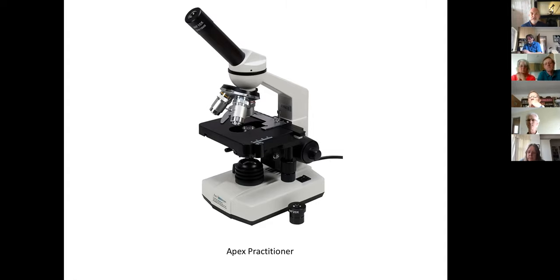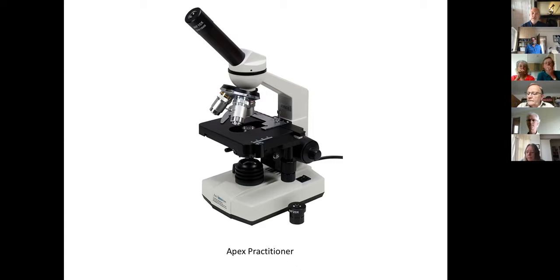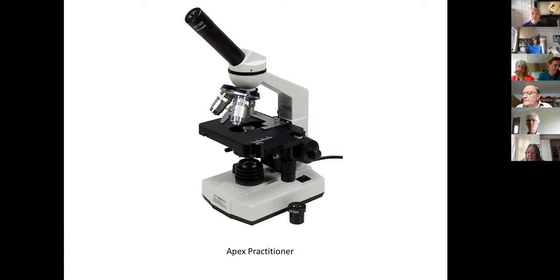There are some basic physical problems with microscopy, mostly caused by magnification — the more the image is magnified, the greater vibration and movement become issues. Ideally you want your microscope still. Microscopes and suspended floors don't go well together. If you have a room with a concrete, solid, or stone floor, that's probably a better location than a suspended floor. My room has a concrete floor but it's on a bus route, so when a bus goes by I get vibration, and when trying to take photographs I have to pause and wait.